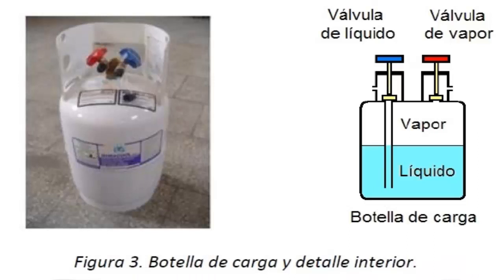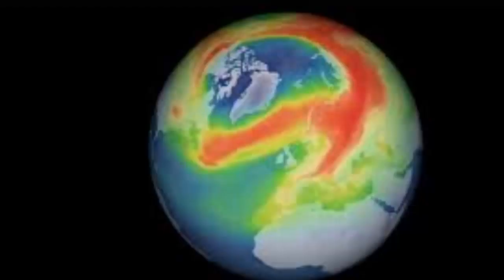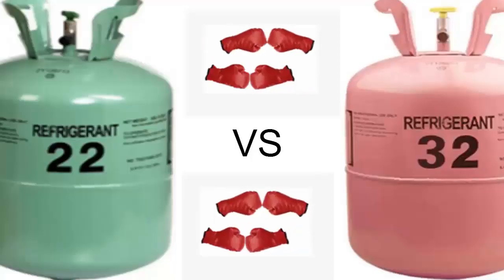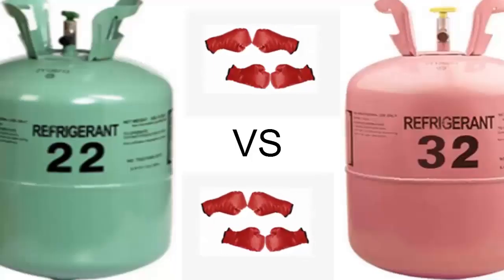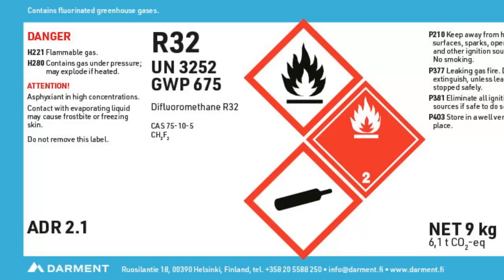The main drawback of R22 lies in its harmful impact on the ozone layer, which is why it is subject to environmental limitations. R22 exhibits a Global Warming Potential of 1760, whereas R32 does not harm the ozone layer and has a GWP of 675.